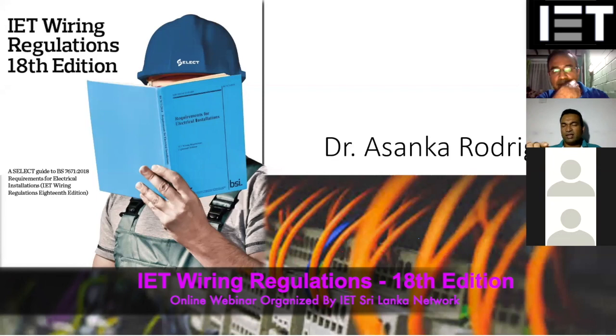And what is the other question? What is the allowable length of the earth wire from SPD? Yeah, allowable length: when you look at the SPD connection, as per the standard, the total lead length, that is from the phase to the SPD and SPD to earth, should not exceed 0.5 meter. The maximum where you can go is 1 meter in the worst case scenario, but the recommended value is 0.5 meter. And the cable sizes are as I mentioned before.